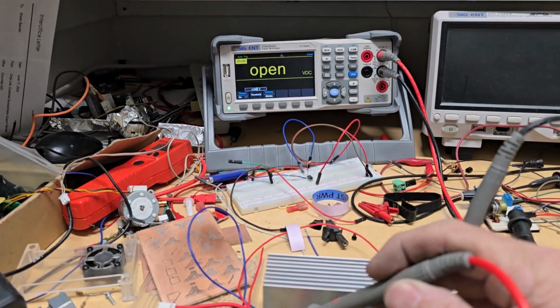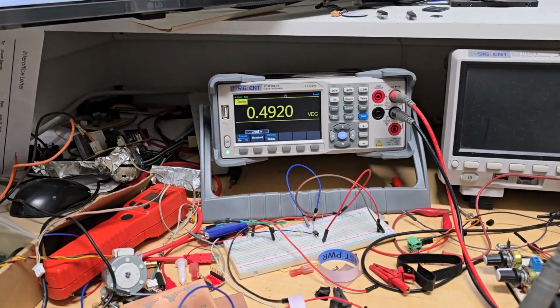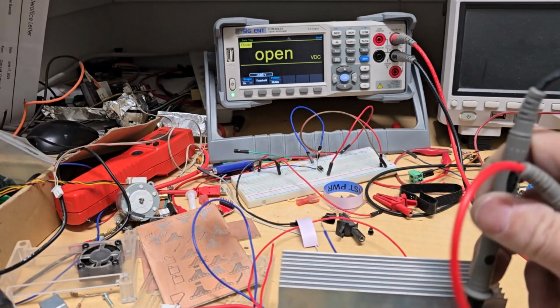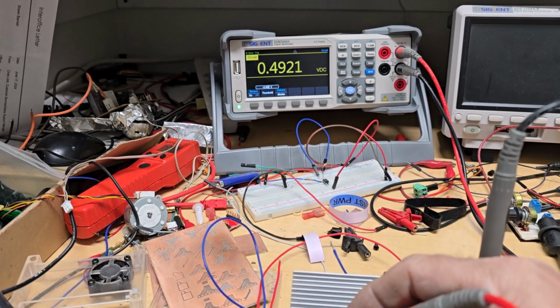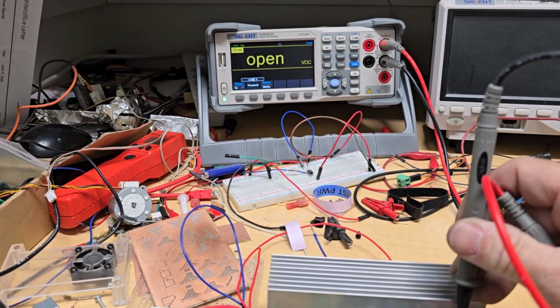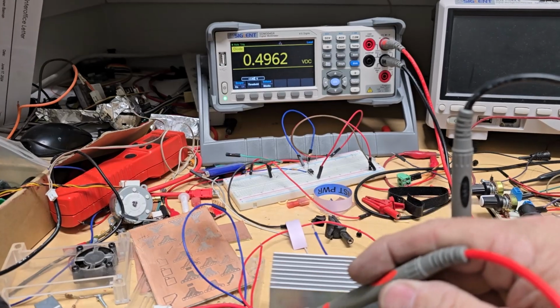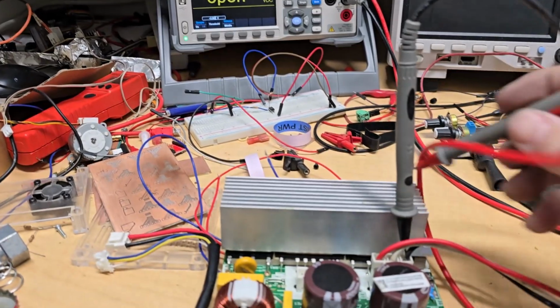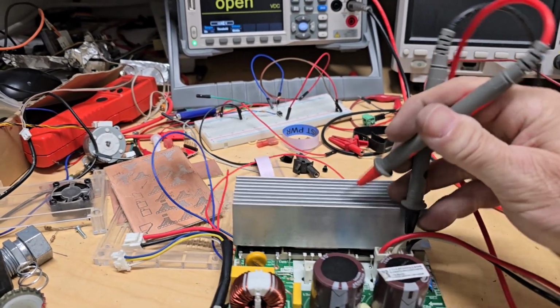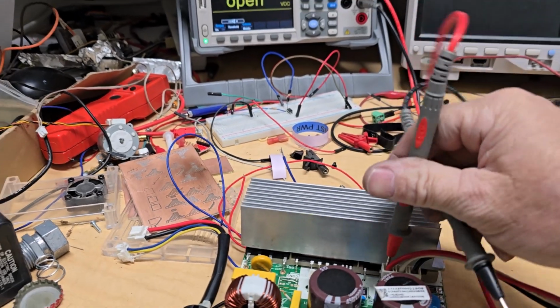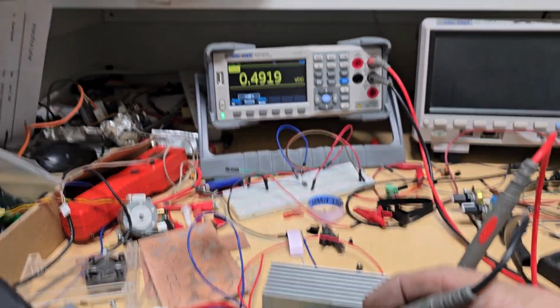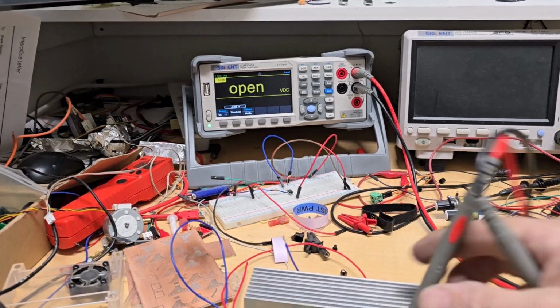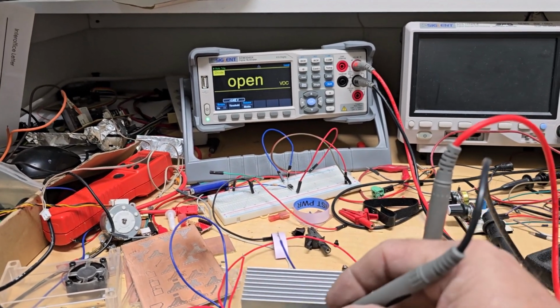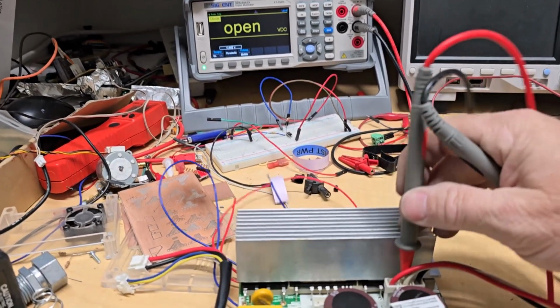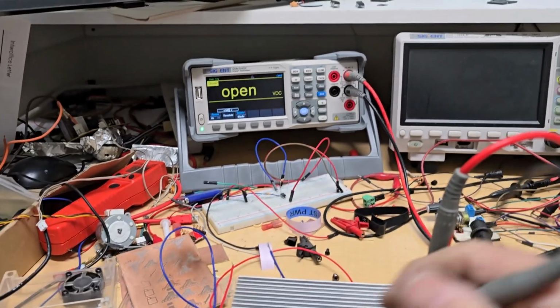So it's open there, now go to the negative side. You've got almost a 0.5 volt drop, on the V and the W, same thing. Then you're going to switch the polarity, so we'll go to the red down here on the U, and then we're going to do the positive - and of course it's open the other way. This is a good module, so I know it's not blown. Same thing over to this one, same thing.